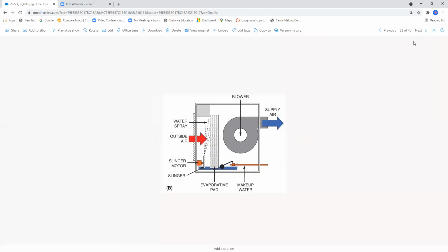This illustration is also located under 36.6. In this particular situation, we have a difference. We have a water spray. You have a slinger motor down here at the bottom, pumping water out of the sump and spraying the side of this media, I guess we'll call it that. And in turn, hot outside dry air is being drawn across this panel or media. And of course, we have cooler air being drawn through this unit and supplied inside the building.